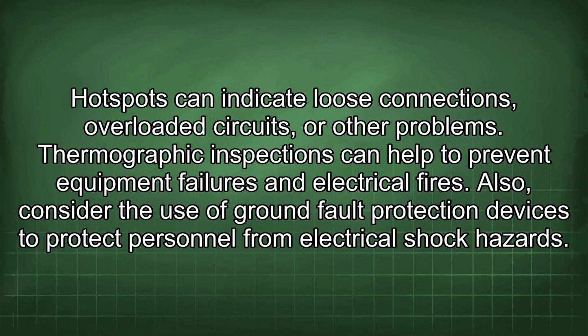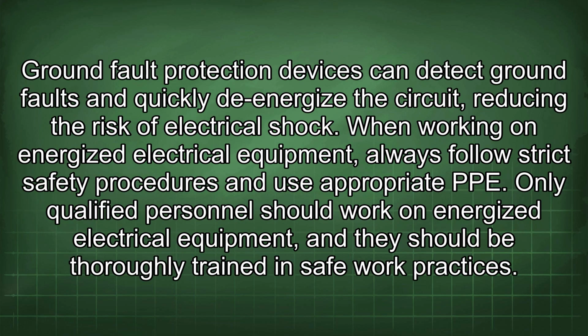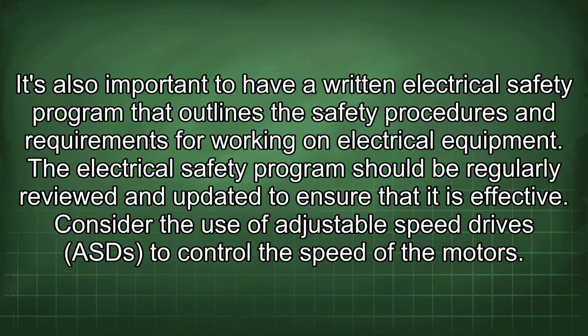Also, consider the use of ground fault protection devices to protect personnel from electrical shock hazards. Ground fault protection devices can detect ground faults and quickly de-energize the circuit, reducing the risk of electrical shock. When working on energized electrical equipment, always follow strict safety procedures and use appropriate PPE. Only qualified personnel should work on energized electrical equipment, and they should be thoroughly trained in safe work practices. It's also important to have a written electrical safety program that outlines the safety procedures and requirements for working on electrical equipment. The electrical safety program should be regularly reviewed and updated to ensure that it is effective.